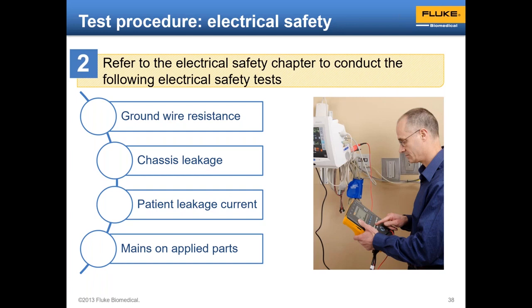You're touching the patient. And by the way, you can demonstrate this very easily by having a patient monitor and touching the patient monitor while you are holding the test lead for chassis leakage. And in fact, if you have a buddy, you can have them touch the monitor and then touch you while you're making this measurement, and you will see that current is flowing. That's because you, the patient, and the caregivers are all electrically conductive. We are not insulators. We are all conductive organisms. So touch current, formerly called chassis leakage, is a measurement that we will make. And as a matter of fact, that is the one test in electrical safety that must always be done, no matter what. You can and should do that touch current leakage test.